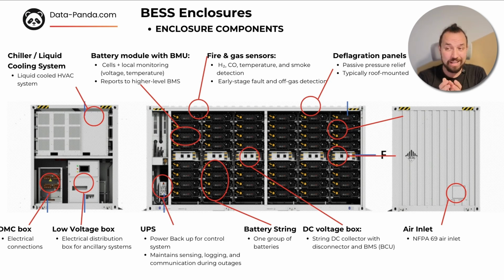And why is it needed? Because imagine the situation, you have hydrogen inside, and there is a fire marshal or somebody opening the doors. So when he starts opening the doors and there is a mix between hydrogen and oxygen, you will get an explosion. So this person who starts opening the door might be well injured because of this explosion. So what we want to achieve, if it happens, is that the gas will not open the doors and hit this person, but the explosion will go on top instead of front. So it's more of a passive system for human safety. We'll talk about design for NFPA 68 and 69 in hot topics, but it's the general approach.